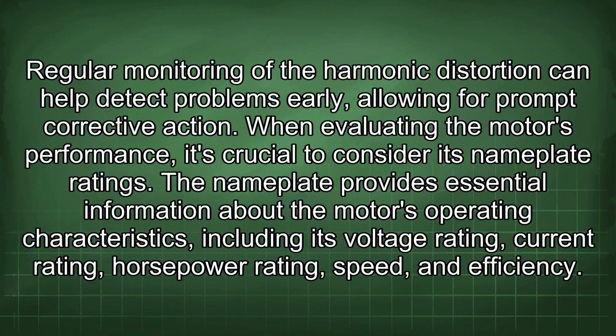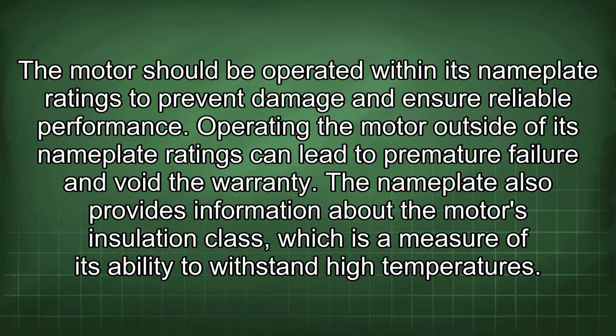When evaluating the motor's performance, it's crucial to consider its nameplate ratings. The nameplate provides essential information about the motor's operating characteristics, including its voltage rating, current rating, horsepower rating, speed, and efficiency. The motor should be operated within its nameplate ratings to prevent damage and ensure reliable performance. Operating the motor outside of its nameplate ratings can lead to premature failure and void the warranty.